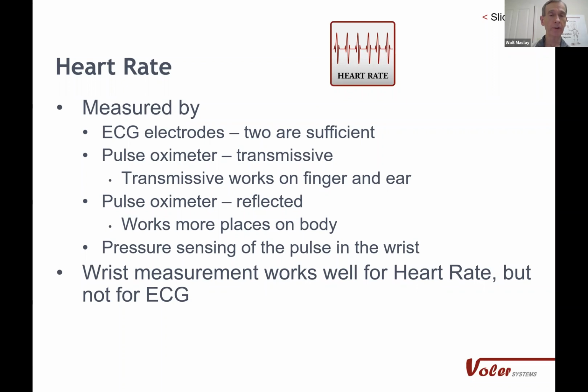Another common way of measuring heart rate is with a pulse oximeter, or at least with a portion of it, the PPG sensor. The pulse oximeter is more sensitive to the heart rate than it is to the oxygen content. And in fact, it has to subtract out the heart rate to measure the oxygen. So it's very good at measuring heart rate. And there's 2 types, the transmissive, which sends light through the finger or through the ear. And there's the reflected, which sends light into the body and looks at what comes back. It works in all the other places in the body, but the signal is smaller. And then you can actually measure heart rate with a pressure sensor. You do that yourself when you put your finger on your wrist to measure your pulse. It can be done, though the other measurements are more reliable, so it's rare.